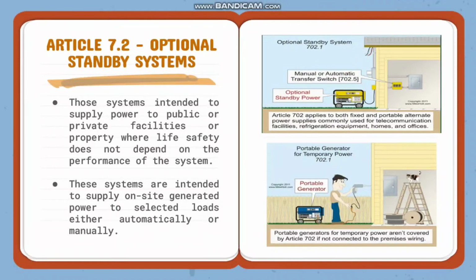Next, Article 7.2 Optional Standby Systems. Those systems intended to supply power to public or private facilities or property where life safety does not depend on the performance of the system. These systems are intended to supply on-site generated power to selected loads either automatically or manually. So taking third priority after emergency and legally required systems, optional standby systems protect public or private facilities or property where life safety doesn't depend on the performance of the system. So these systems aren't required for the rescue operations.